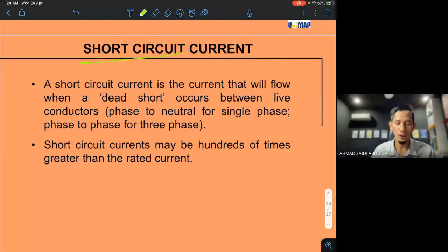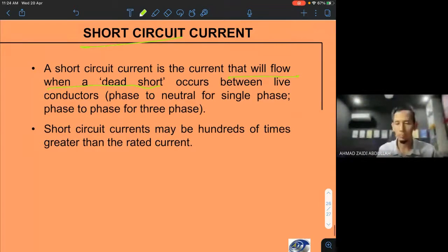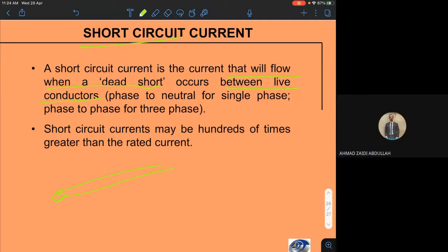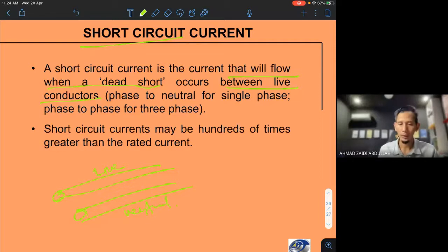Short circuit ni apa pula? Short circuit is the current that will flow with a dead short. Dead short ni apa? Laluan yang disentuh lah, between live conductors. Okay, let's say you have two cables, kan? And this one is live. And then let's say this is the neutral, kan? Ataupun let's say for this one for single phase lah, satu phase. Kalau three phase, we also have three phases, kan? R, Y, B. So it is possible this one touches this one also. We call it short circuit.